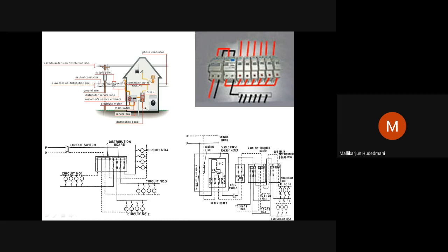Now my intention is to explain what the meter board is. The meter board is the termination where the energy meter is fixed. To the energy meter, we get input from the distribution company service. This service may be overhead or underground. These cables come and get connected to the energy meter. This connection is protected and shall not be tampered with. So the first electrical contact of the distribution company lands exactly on the meter board. It is sealed and protected.